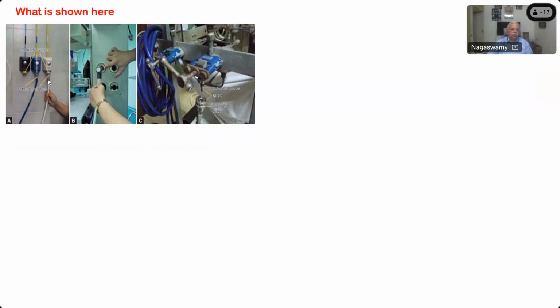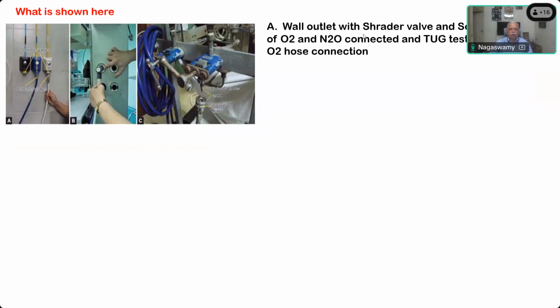Whereas here it is on the reverse side. The probe is going here and the Schrader valve is fixed to the wall. Whereas here the probe is fixed to the yoke assembly and the Schrader valve will be inserted here. This is an older type of connection.